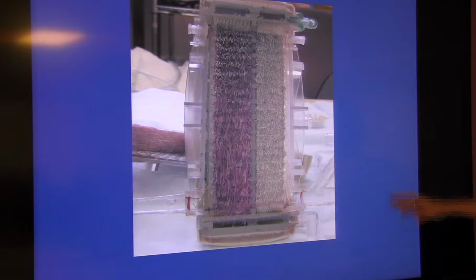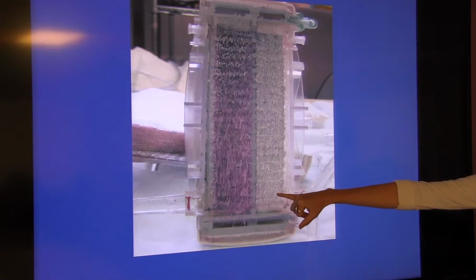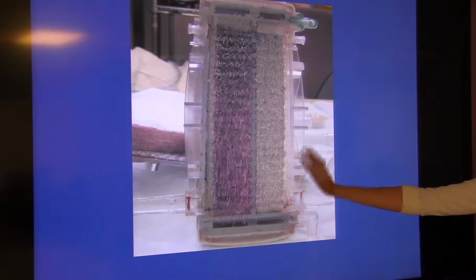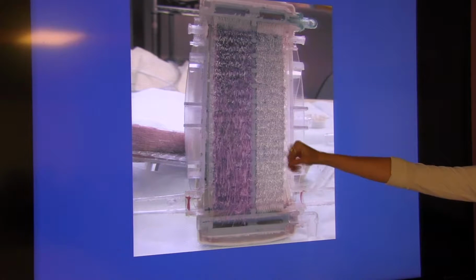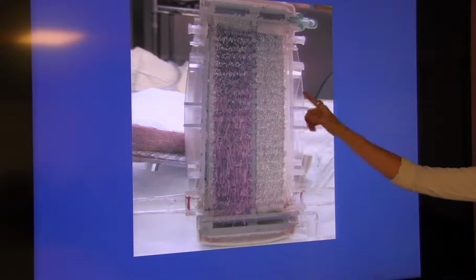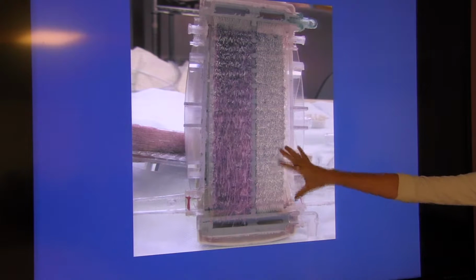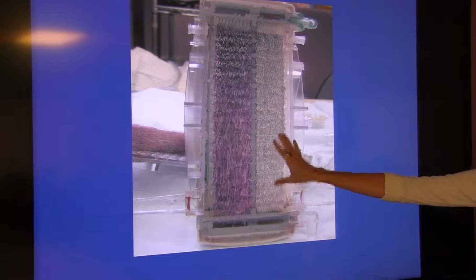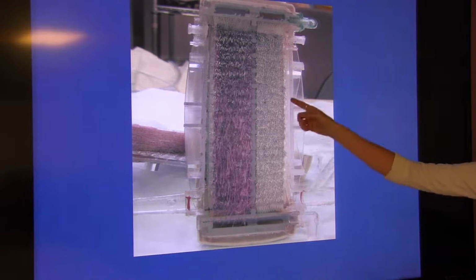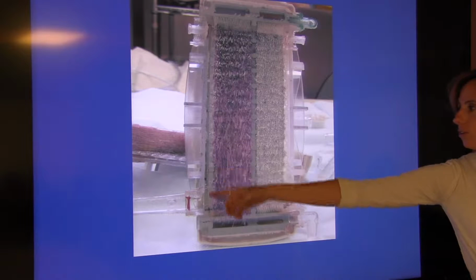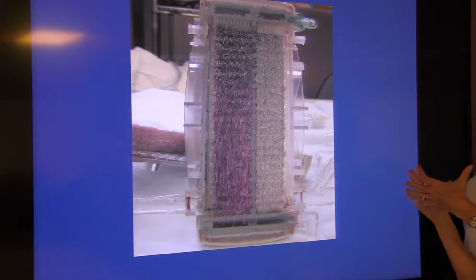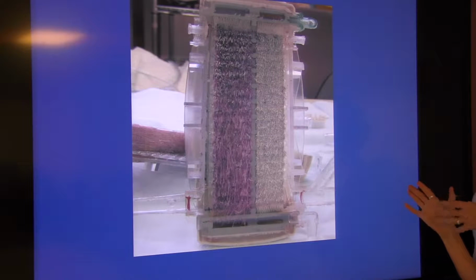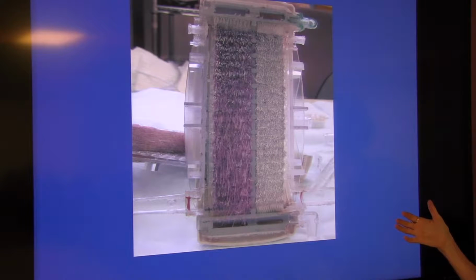Because when I say act as the filter, so this is what that oxygenator looks like if you cut it from the top of the diamond down. So these are all the microtubules that are running through it. And so the blood is flowing across these microtubules. And then some of the microtubules have water running through them, and some of them have gas running through them. I forget which side is which in this picture, but you can see how many of them there are in there. And so there's a face plate here, there's also a plate here, and then a back plate here, and so it compresses all those together, because the more surface area of contact you have between the gas and the blood, the more capacity you have for oxygen delivery.